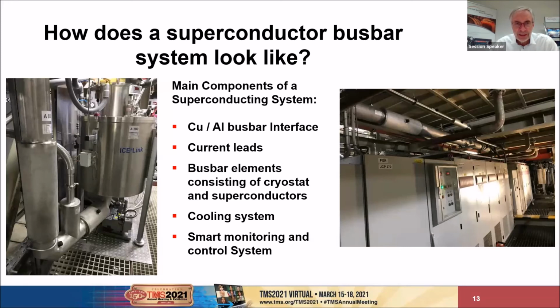On the left side picture, you see a current lead. You see the name IceLink on that vessel. And here you see the transformation from ambient temperature to liquid nitrogen temperature. From the bottom, the busbar system is going away and then up. So we have vertical and horizontal parts connected with an angle. And you see that this angle is right sharp. It's a 90-degree angle, but we can also produce every direction of the angle.